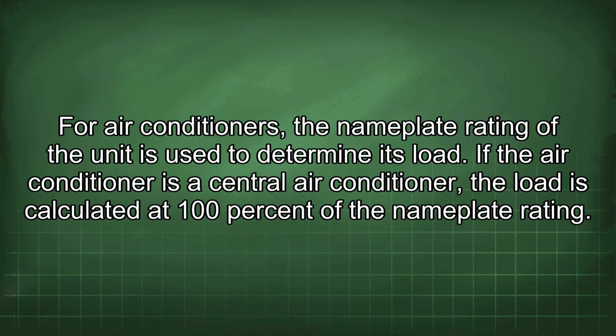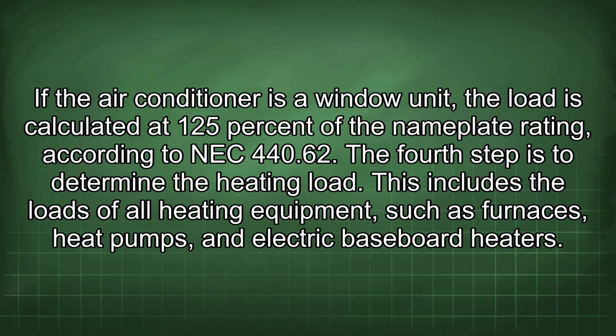220.54. For air conditioners, the nameplate rating of the unit is used to determine its load. If the air conditioner is a central air conditioner, the load is calculated at 100% of the nameplate rating. If the air conditioner is a window unit, the load is calculated at 125% of the nameplate rating, according to NEC 440.62. The fourth step is to determine the heating load.